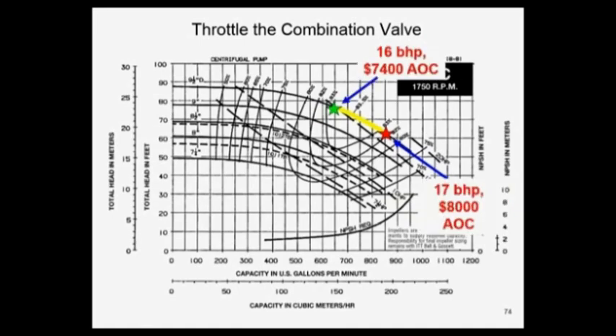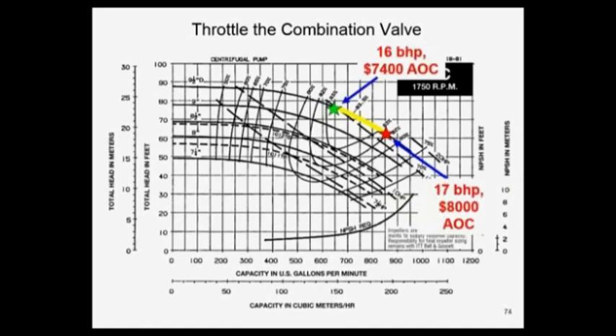Did I save any money? A little bit. At six cents a kilowatt running constantly, I just saved $600 a year, dropped it from 17 brake horsepower back to 16, and I've got design flow. I'm giving the engineer, I'm giving the owner exactly what they asked for. 76 feet of head, 650 GPM, and I've saved $600.